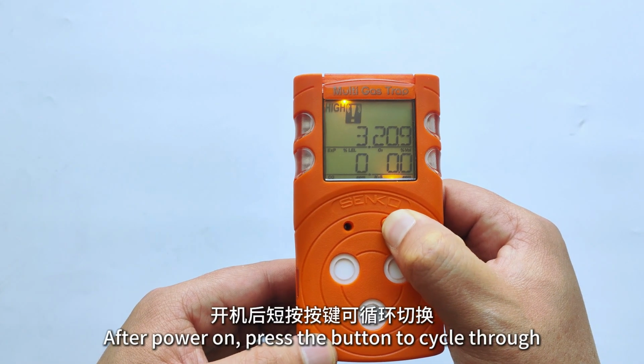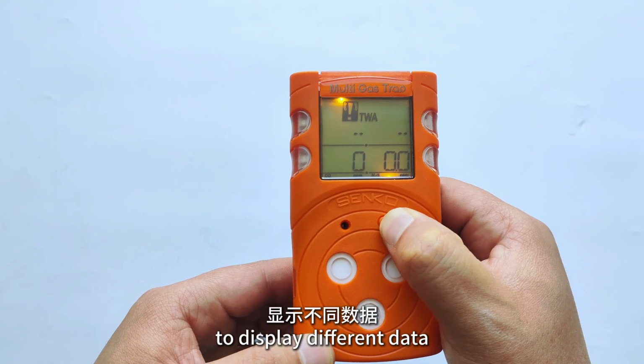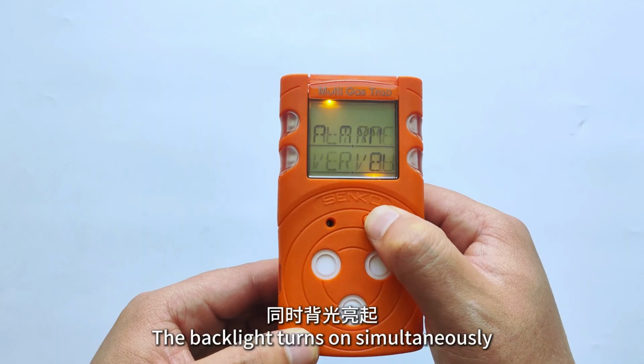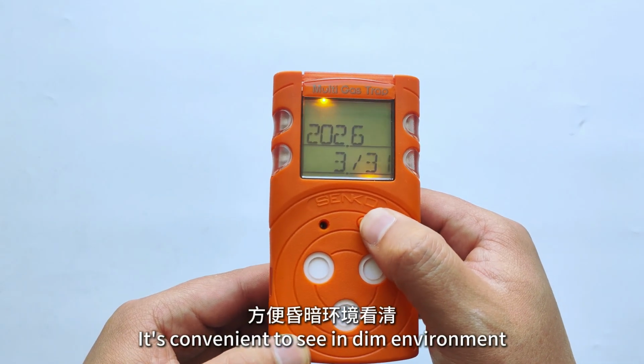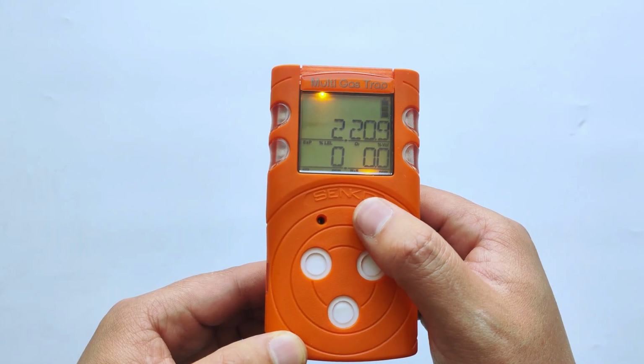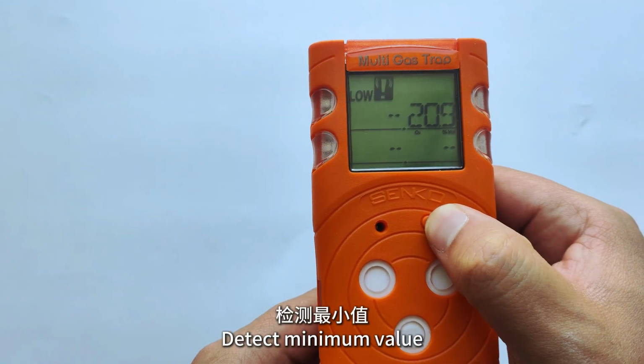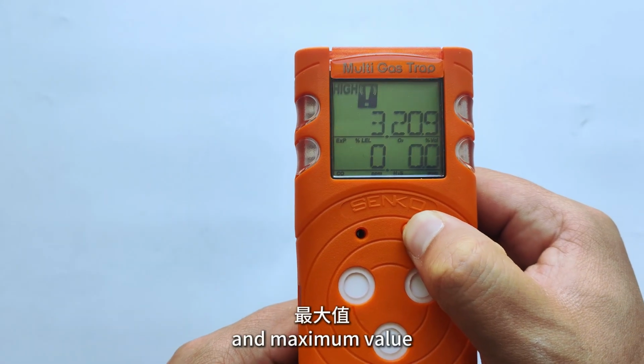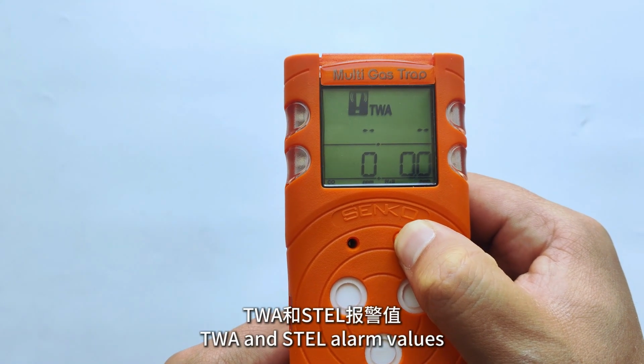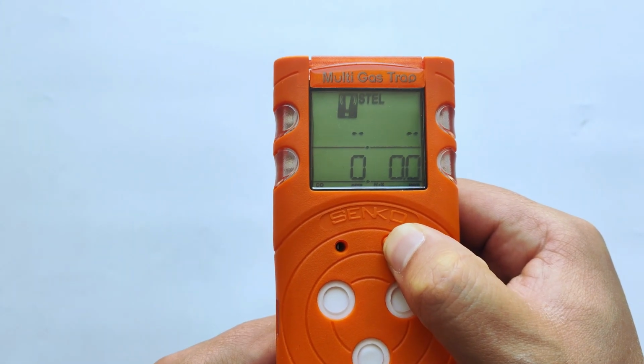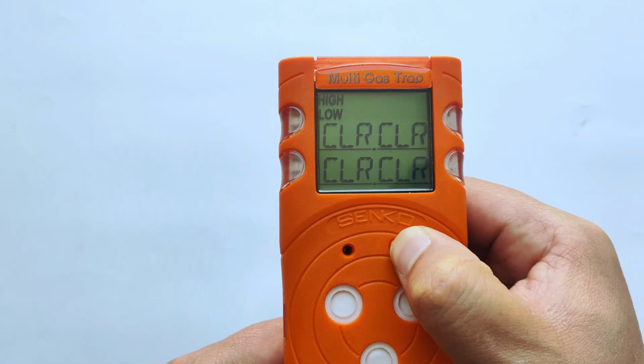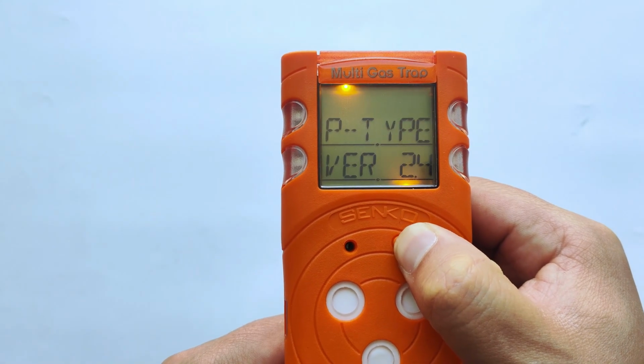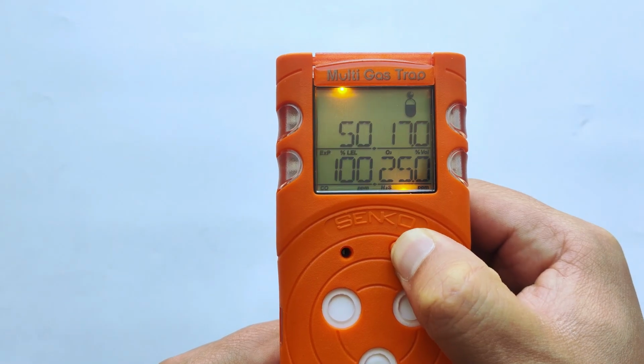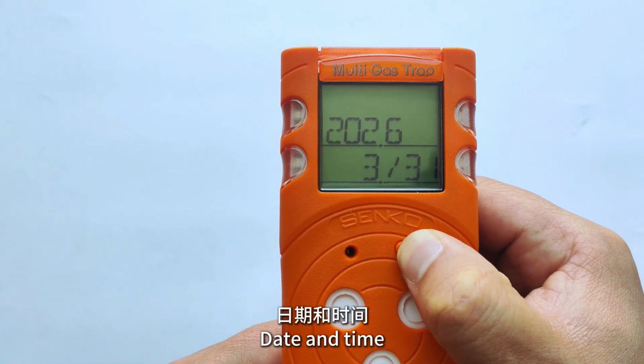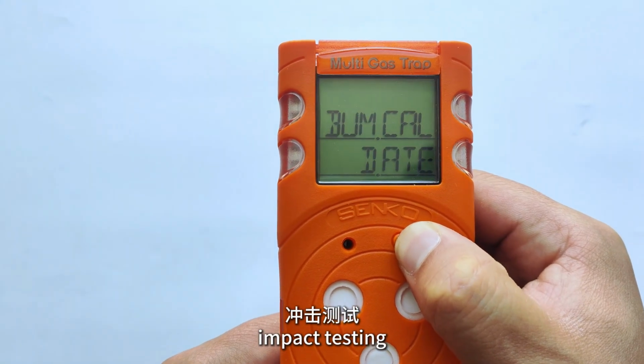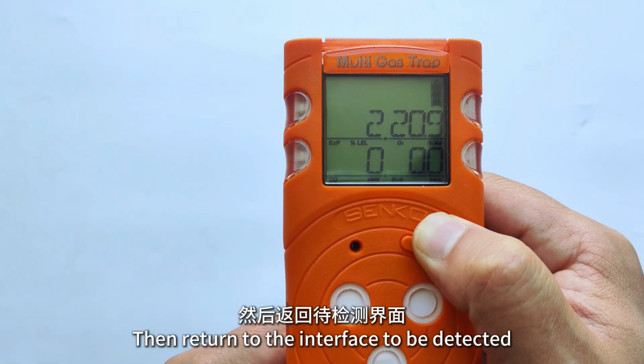After power on, press the button to cycle through and display different data; the backlight turns on simultaneously. It's convenient to see in dim environments. The content displayed in the loop is detect minimum value and maximum value, TWA and STEL alarm values, clear alarm value, set the alarm value, firmware version, set range calibration, date and time, impact testing, then return to the interface to be detected.